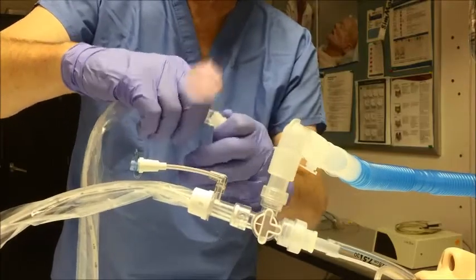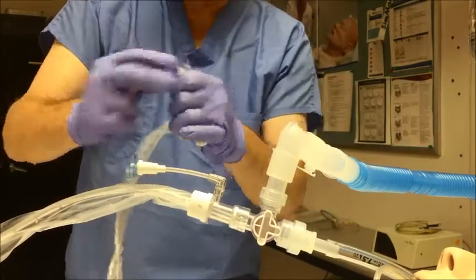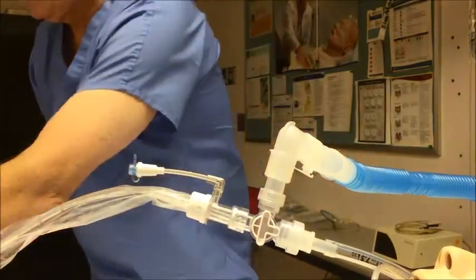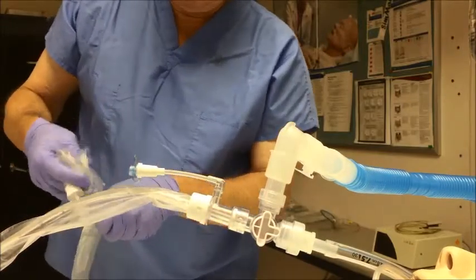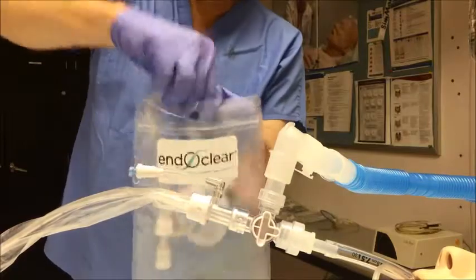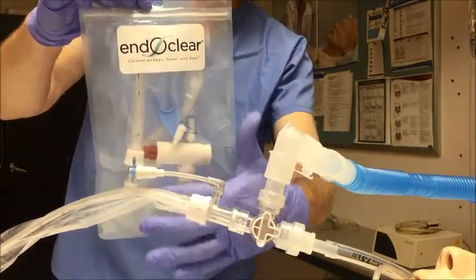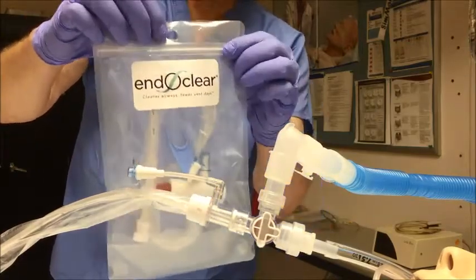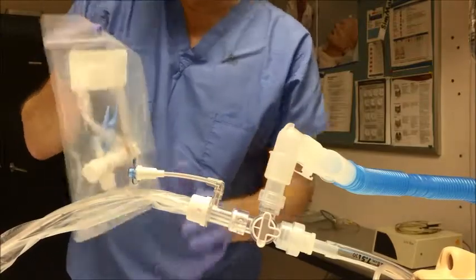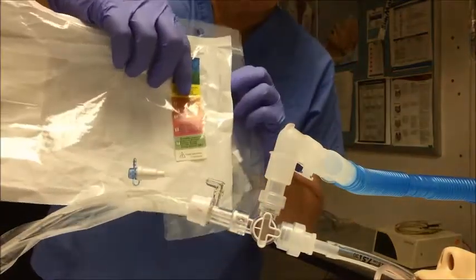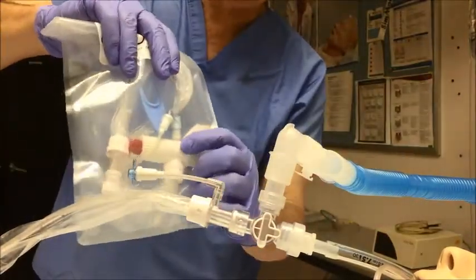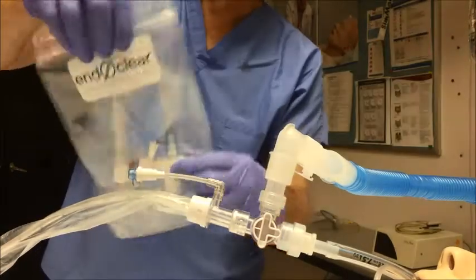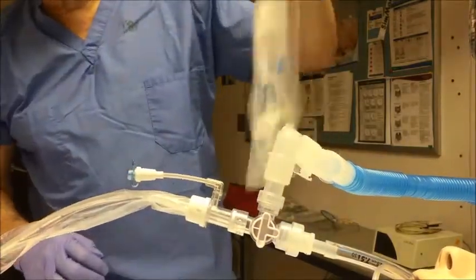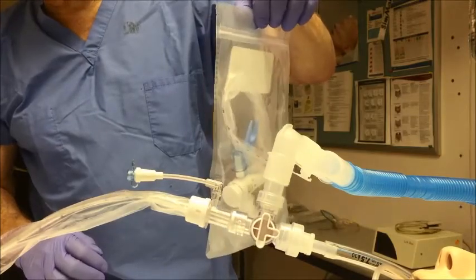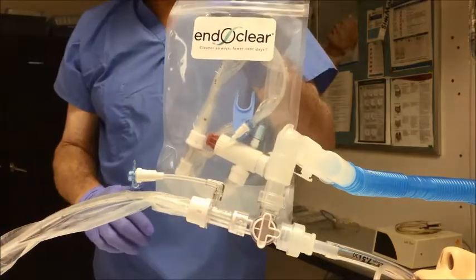The sterile cap goes on the 72-hour Liberator device, which is then stored offline in a storage bag that says endOclear. You're able to see what device is inside and in fact read all the numbers, including the 72-hour sticker that would be placed right here on the suction control. And there is a hole in the bag so that it can be hung up on the ventilator or with the oral care or in any convenient hanger in close proximity to the patient or where it would be used.